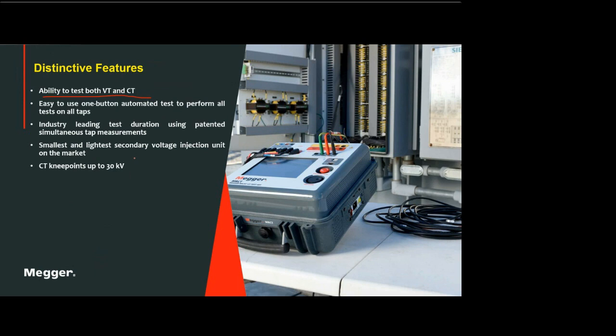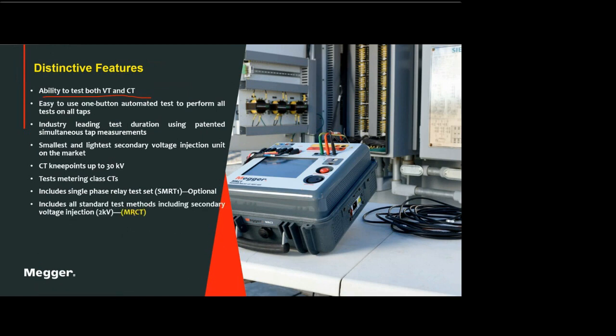It can do CT knee point up to 30 kV. It can test metering class CTs. It includes a single phase relay test set, but it is optional. So the MBCT and MRCT can have the single phase relay test set included. So that is optional, of course. It includes all the standard tests, up to 2 kV for the MRCT. And then you can do group testing, demagnetization, knee point. Like I've said, in just one go, you can have all those results.